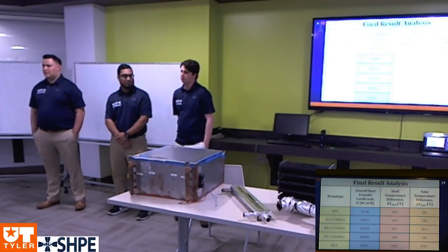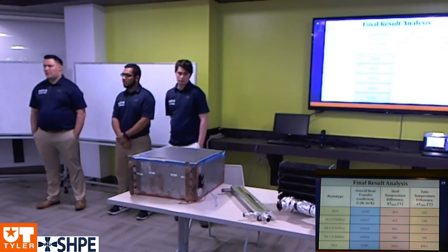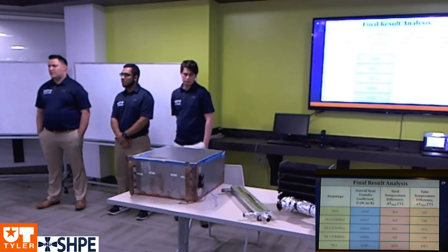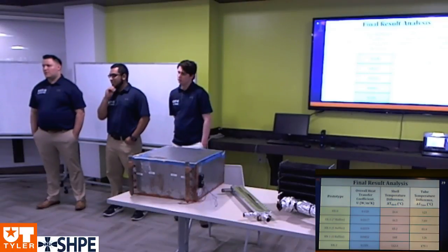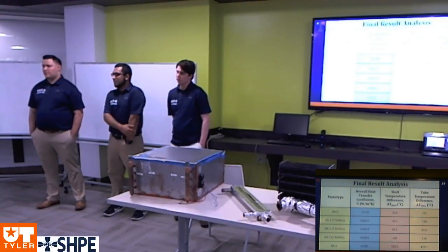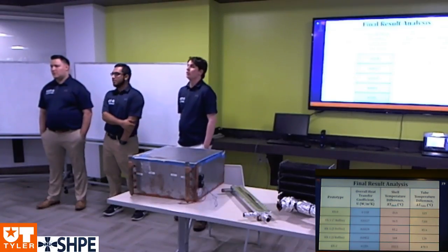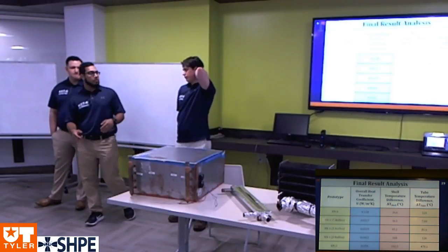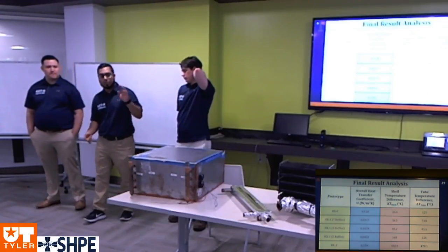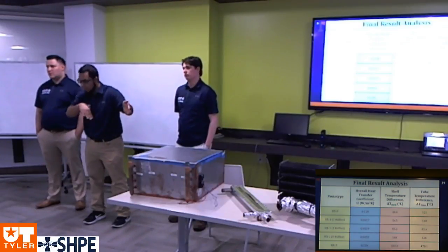And on the maintenance side, another thing: when you have a heat exchanger with the shell and tube arrangement, it has so many drains, and the water comes with so much scale, and over the years you need to clean it, otherwise it will be jammed. So did you have a chance to look at that aspect? For the designing portion, the filters, well, not just that, but we made it sort of modular, where you can take the top off and you can see everything inside.